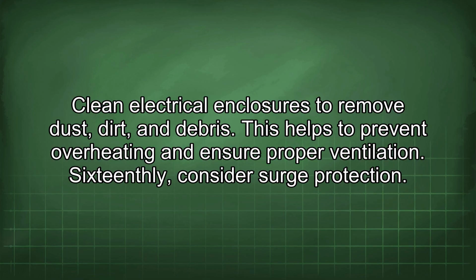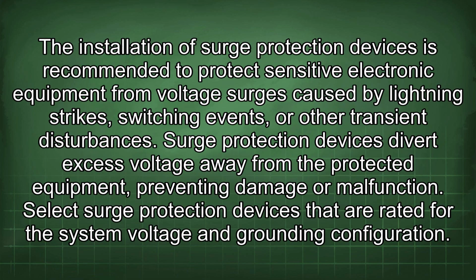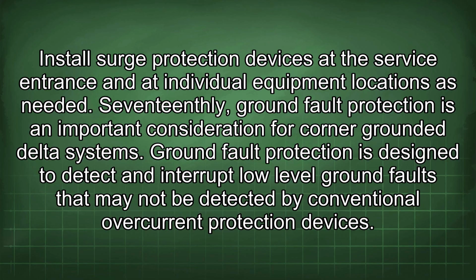16thly, consider surge protection. The installation of surge protection devices is recommended to protect sensitive electronic equipment from voltage surges caused by lightning strikes, switching events, or other transient disturbances. Surge protection devices divert excess voltage away from the protected equipment, preventing damage or malfunction. Select surge protection devices that are rated for the system voltage and grounding configuration. Install surge protection devices at the service entrance and at individual equipment locations as needed.